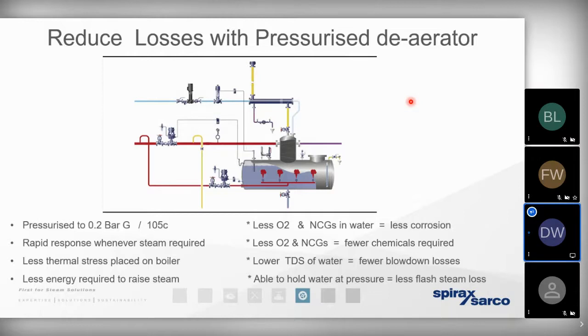But ultimately, it means that we've now found a way that we can actually utilize that flash steam. By directing those flash steam losses back towards the pressurized deaerator, it ultimately means that we can use that flash steam, and we're moving very, very close towards a point where we've got a zero loss system. Of course, we may be using a very, very small amount of steam as that's being used to move the air across the air vent, but we can typically condense that very small amount of steam in a very, very similar exhaust vent condenser.